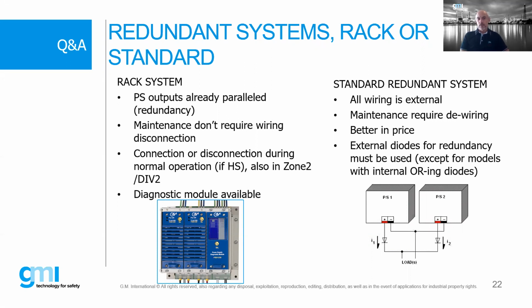While if you use a rack system on the left side, the power supplies are already in parallel, so you don't need to parallel them yourself. The maintenance doesn't require wiring disconnection. It means I can remove one module, and the other will take over the power. This is also possible during normal operation, also in zone 2 or div 2. And there is also a diagnostic module available. So there are two different schools of operation, but you see the differences. The difference is mostly in the wiring and also the OR-ing diodes for redundancy.